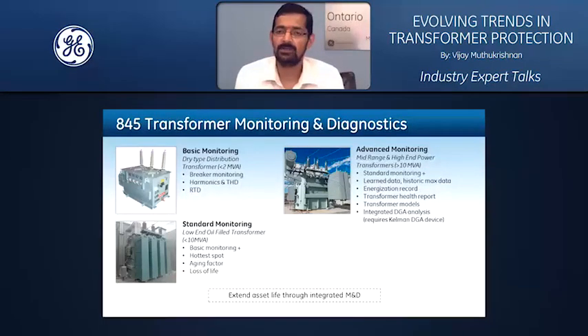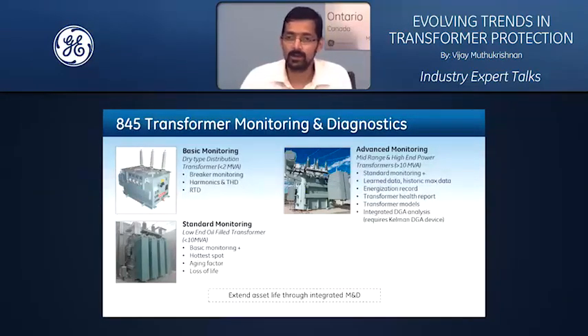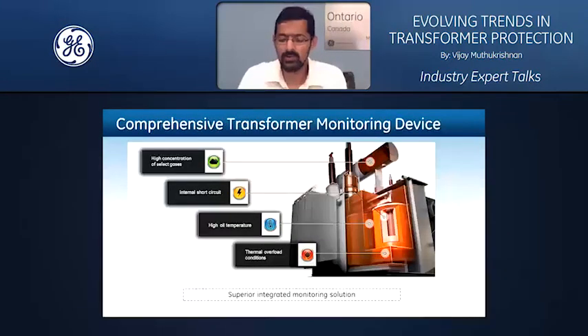Say, for instance, you have an incipient fault developing in a transformer after a true fault condition. The relay can detect a true fault, and it has the ability to know what happened before the fault, electrically and chemically, and what is happening in the transformer after the fault, electrically and chemically. If this data is presented to you in a meaningful and interpretable way, you have a very powerful analytical tool in your hand to make decisions about the condition of your transformer, take preventive actions, and over the life of the transformer, put in practices that allow you to extend its life. So the core idea behind this integrated monitoring and diagnostics is to enable you to extend the life of the transformer.